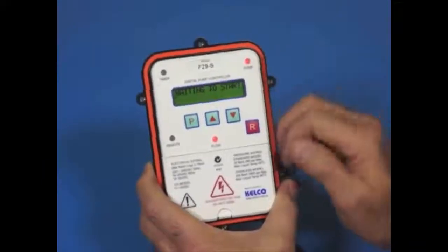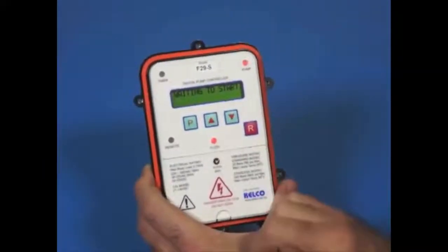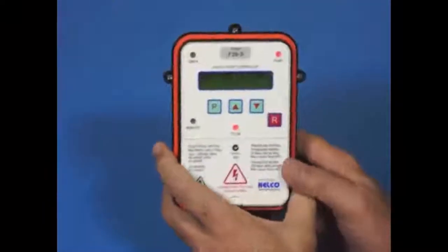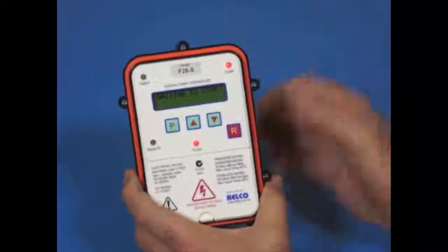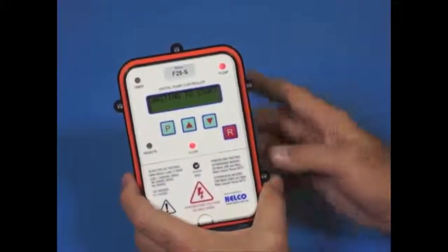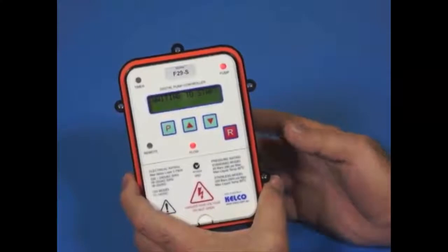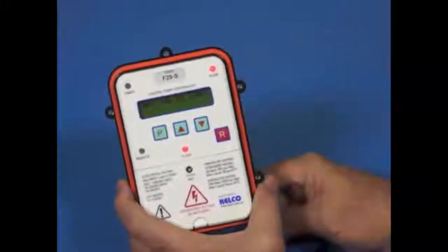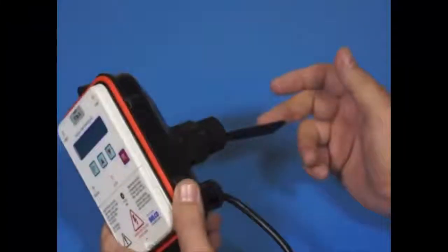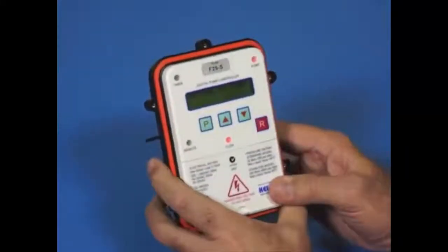Pump's stopping. Our pump lights come on red because we've got no flow. And it'll sit there now, waiting to start. So in essence, that's the simple function of the F29. Overrides its off-state, gets the pump started, allows time for it to establish flow, then hands command over to its paddle. If the flow is interrupted, it tolerates the paddle bouncing back and forth. If the flow is genuinely lost, the F29 will shut the pump down.